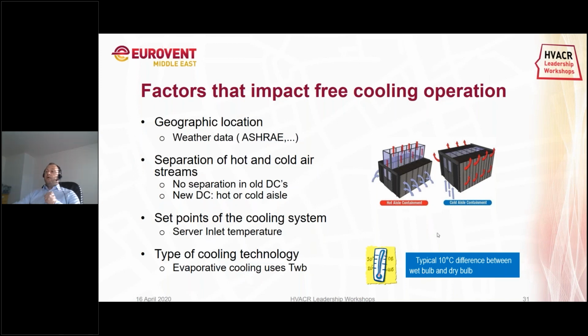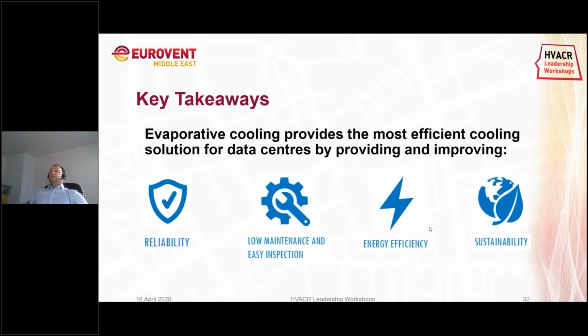So we are now reaching the end of the presentation, and I want to give you some key takeaways. I want to tell you that evaporative cooling is one of the most efficient cooling solutions for data centers by providing and improving the reliability by using Eurovent certified evaporative cooling products. You can be assured that the performance is as mentioned on the data sheets. We are looking for very low maintenance and easy inspection units, preferably with cross-flow units. You can have an easy access and very easy maintenance. The energy efficiency is very important, and evaporative cooling is still the most energy efficient method of cooling.